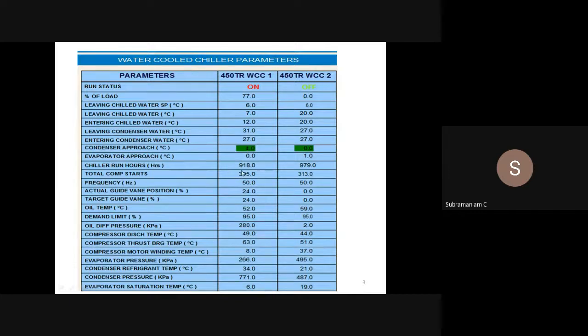Evaporator approach, chiller run hours, compressor number of starts, because the chiller technician will come and see whether my starts and run hours are in proportion. Because if you have got too many starts, you are going to have a problem with the winding of that compressor motor, right? Then what is my guide vane? Actually, it is a centrifugal compressor chiller, because we are having guide vane. Actual guide vane position 24%, oil temperature, demand limit.